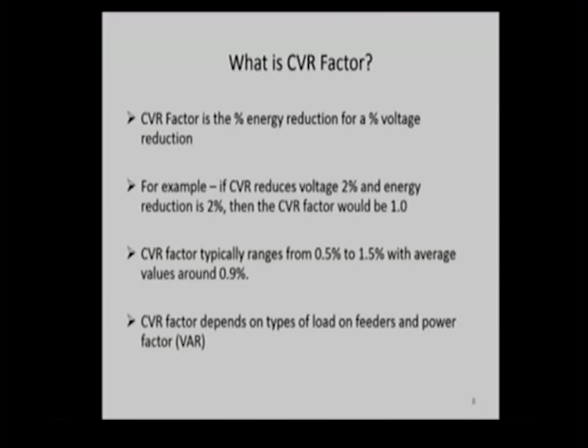So now I'm going to talk for a few minutes about how the voltage ranges can be reduced. First, we need to continuously monitor the feeder voltages and use capacitor banks and load tap changers to adaptively reduce the voltages on each feeder at the substation. And I have a little picture there. A load tap changer is a big transformer that can be adjusted remotely. So it has taps that can be raised and lowered, which will raise and lower the voltage on all of the feeders from that substation.